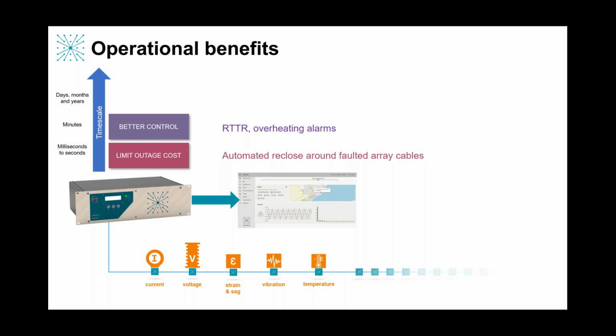But when you take all of that data and you store it and you build a history over time, you can trend line that data, and you get into the world of prognostics. That says there is a way to reduce scheduled maintenance because our sensors are so sensitive that we're picking up clues about impending failures of individual components in the electrical system. And that means we're spotting faults before they happen and warning of when it's appropriate to go and do advanced replacements, and also eliminating sources of cable damage, which is still the industry's biggest cost factor and probably the hardest thing to predict or control.